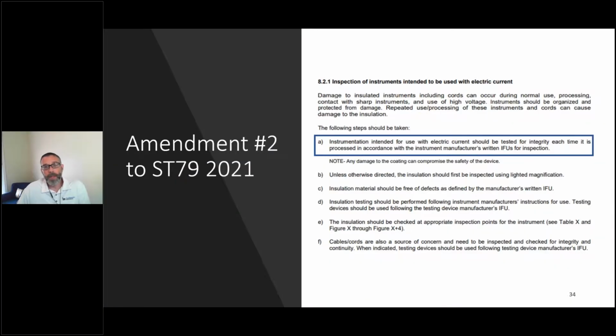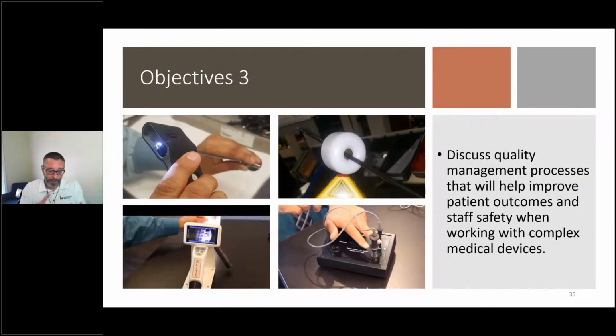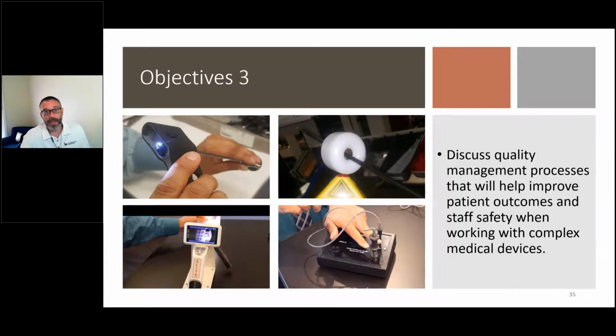Next slide. We had to put this in because it's new. There were four new amendments that came out in 2021 to ST79, and Amendment 2 was about inspecting that insulated surgical devices have finally gotten their own spot. So this is where we need to be: instruments intended for use with electrical current should be tested for integrity each time they're processed. Think about that, that's your cords, your laparoscopic instruments, your bipolars. Those are all ESU devices, they're all electrical devices, and they all need to be checked each time. Now Kevin is going to talk to us about adding some quality to our inspections.